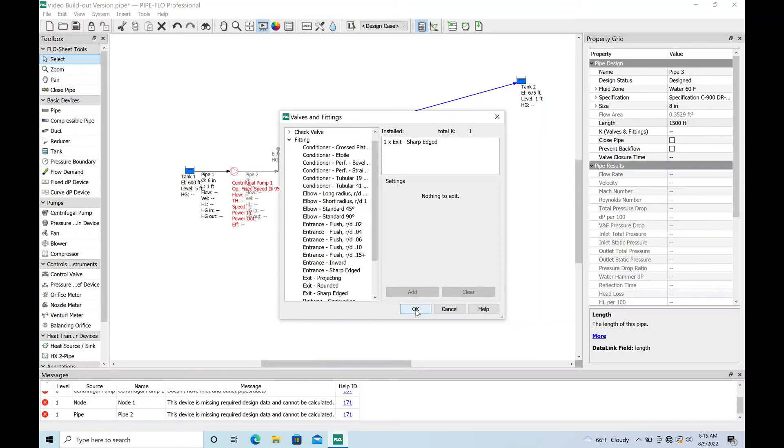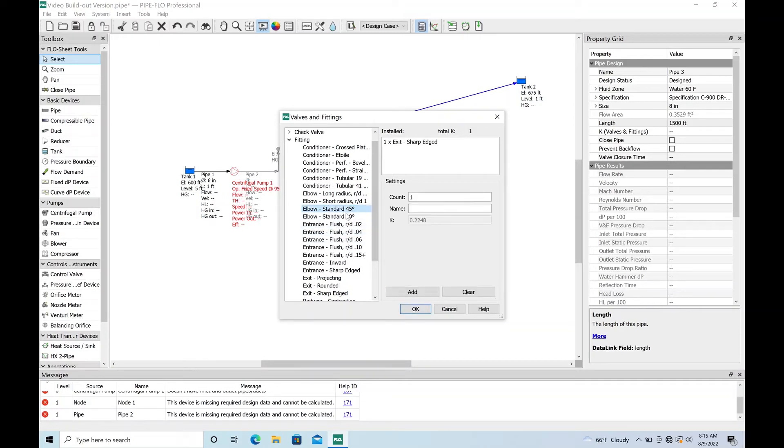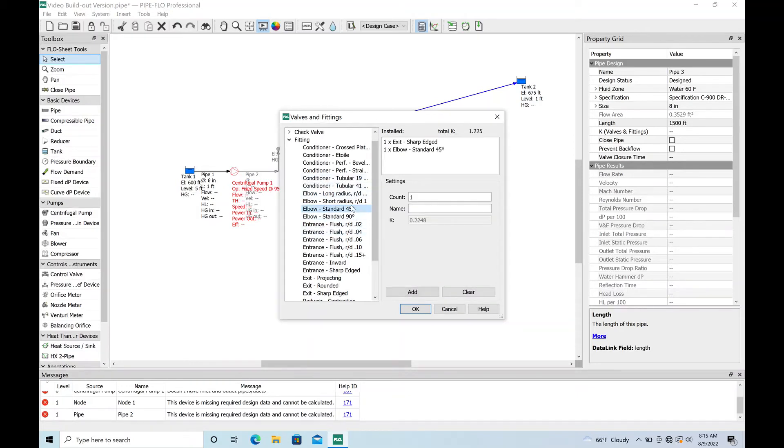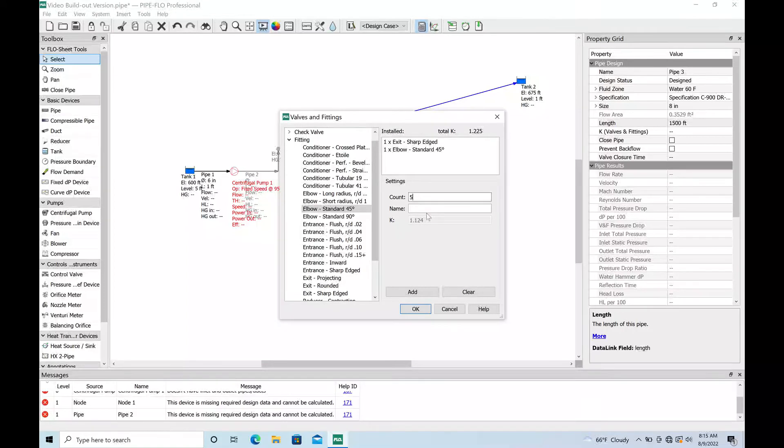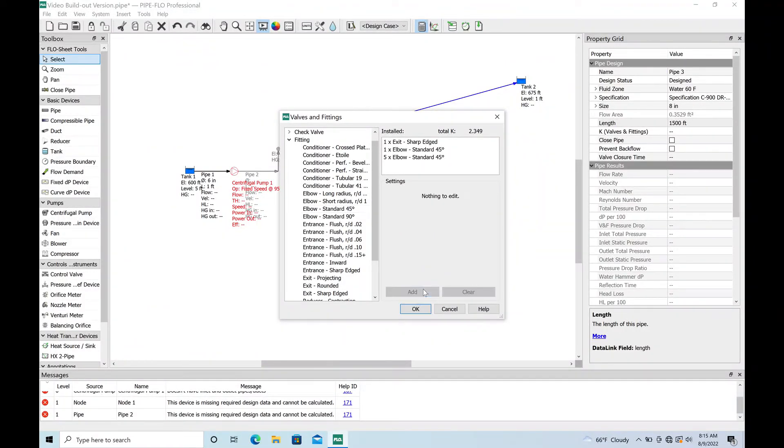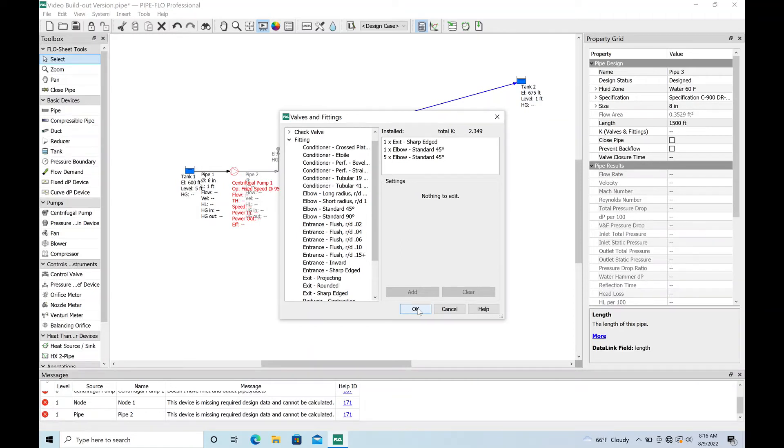A lot of times, a lot of engineers will go back and forth - do you put the fittings on the force main in here? I do generally if I know where they are. So we'll go and throw out a couple 45s. A lot of my clients like 45s. You can either do that and do it a different time. Let's say there's like five of them, you can just put five and just add, boom done. That's sort of helpful, it makes your model a little bit better. Does it really make a huge difference? No, you really won't notice one way or the other and I've seen models built both ways.